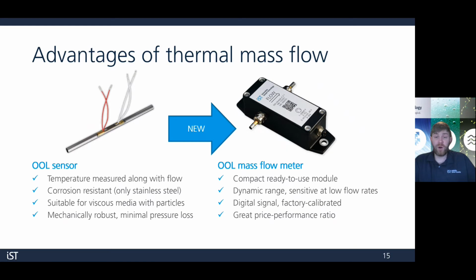On the right side, we have the OOL mass flow meter. Inside, it uses the same type of OOL sensor, and it covers a dynamic range and is very sensitive at low flow rates, making it a great choice for leakage detection and dosing. It comes factory pre-calibrated and delivers a digital I²C signal with temperature in degrees Celsius, the raw power in milliwatts, and our flow rate in kilograms per hour. It offers a great price-performance ratio and is simple to install in many applications. And like I mentioned before, no moving parts.